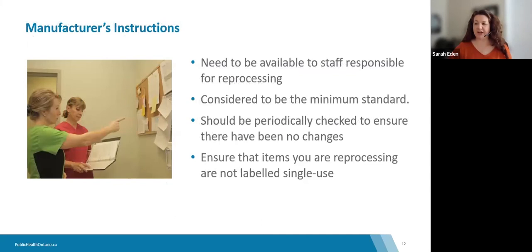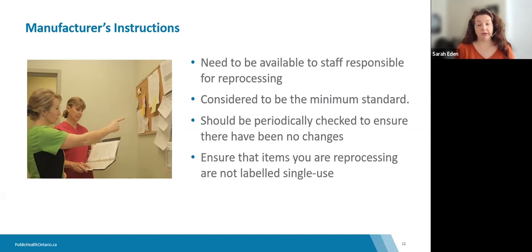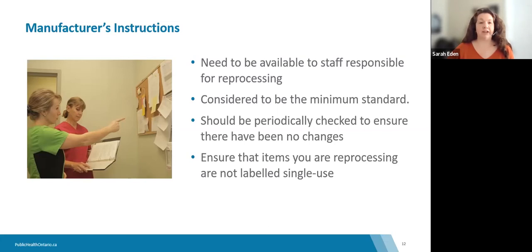Manufacturer's instructions need to be available and accessible for the staff responsible for reprocessing — for example, in a binder in the area where reprocessing is being done. Those manufacturer's instructions are considered the minimum standard and need to be periodically checked to ensure they are up to date, as changes may occur. Someone should be responsible for reviewing them and checking for any Health Canada indications or recalls, verifying that you have a periodic review, that those instructions are still applicable, and that you don't have any outdated instructions for equipment no longer in use.